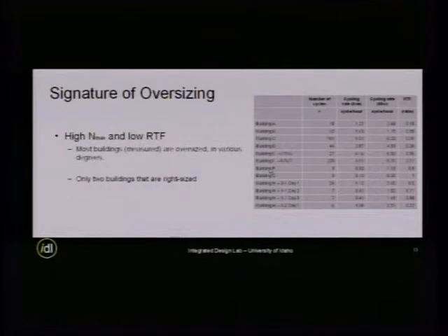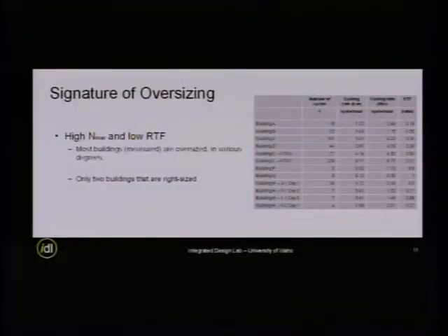We have examples where the cycling rate is zero, which means that it switched on once and never turned off throughout the day. And this is the right size unit. As you can see, the runtime fraction is 1, which means it runs all the time. Only two buildings, I think, are right sized. These two, F and G, are right sized.